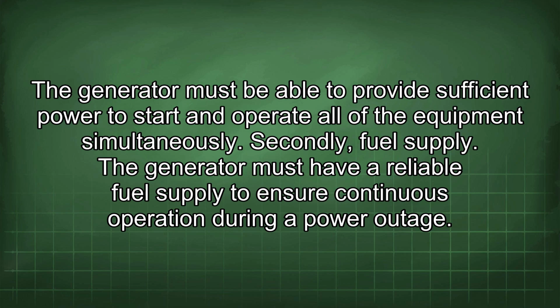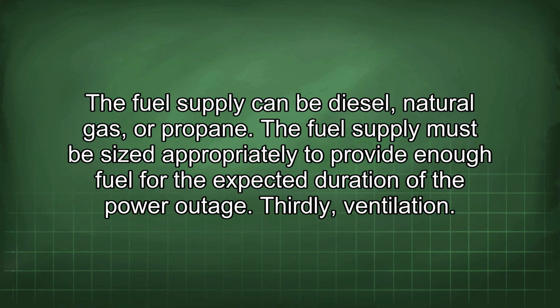Secondly, fuel supply. The generator must have a reliable fuel supply to ensure continuous operation during a power outage. The fuel supply can be diesel, natural gas, or propane. Fuel supply must be sized appropriately to provide enough fuel for the expected duration of the power outage.